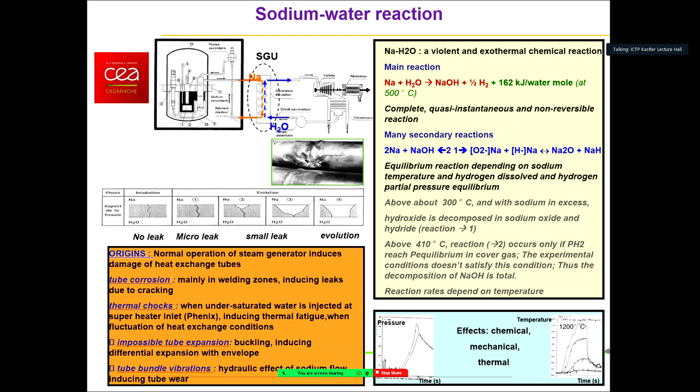So we have developed these rules of operation for the reactors, particularly for Superphénix, and they were considered as reliable methodologies to avoid any subsequent accidental situation. For example, on Superphénix, we never faced a sodium water interaction during 12 years, no leak. On Phénix, we had five incidents with a very small amount of water, maximum 4 liters, but there was no serious incident induced by a pressure wave, for example.